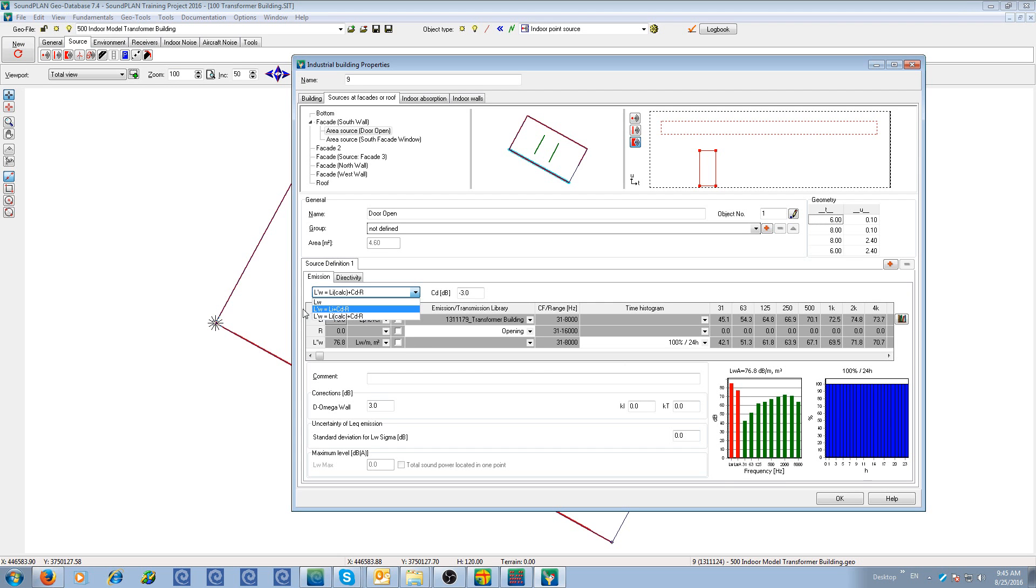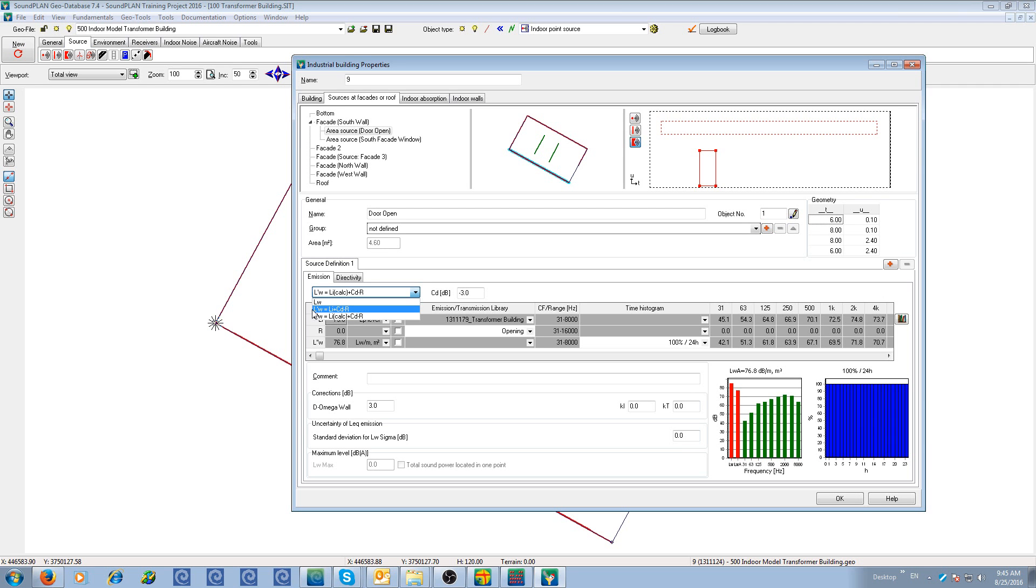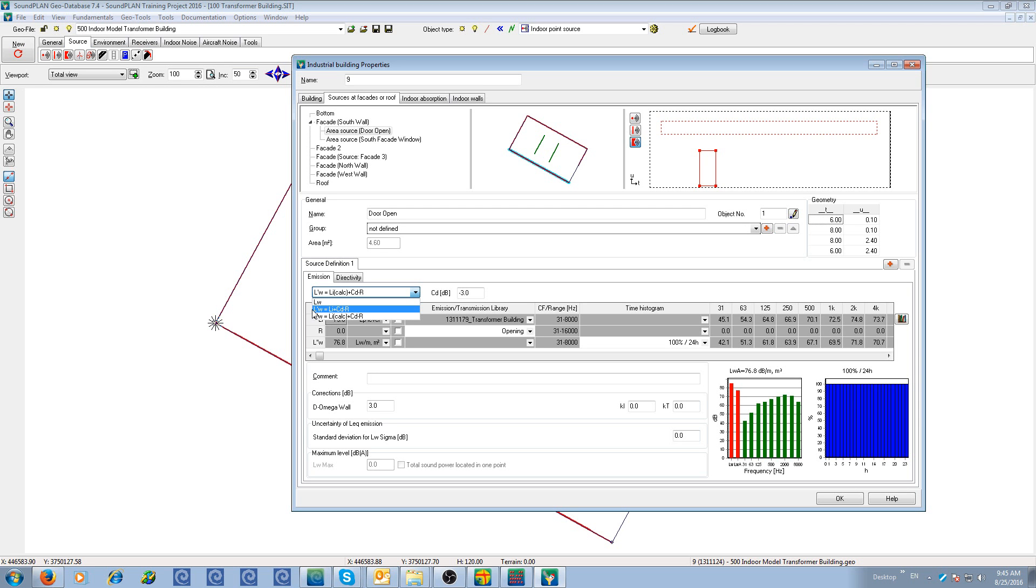The second option L'W stands for intensity or sound power per square meter. This can be calculated with a given interior level. The interior level has the index Li, so a level in interior. From a planning standpoint, we can say this transformer building has an interior level of 80 decibels or 85 decibels or 90 decibels with whatever spectrum. Then the program will use that interior level, correct for the room constant, the CD, and the transmission loss from inside to outside.